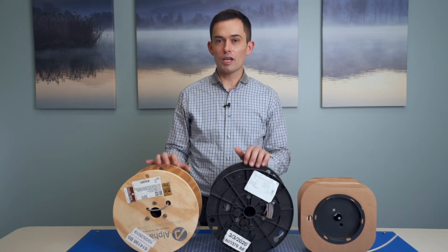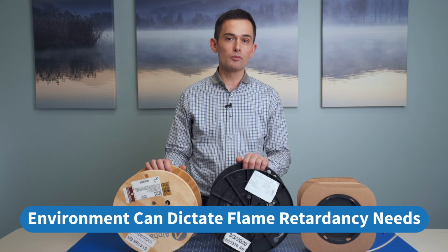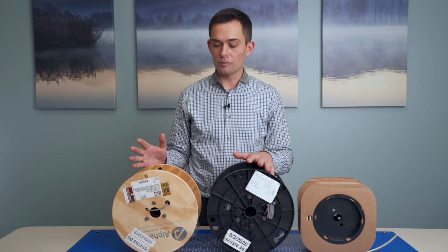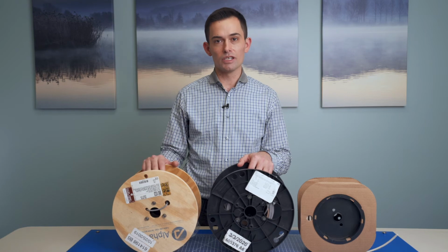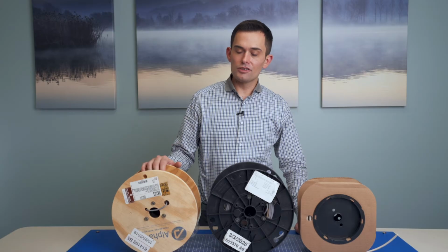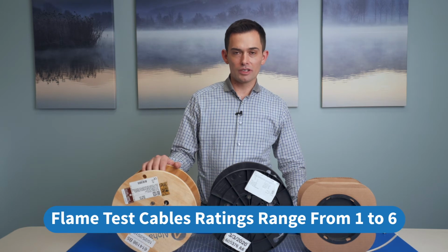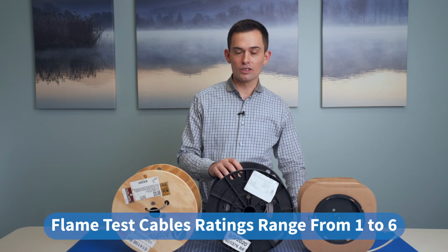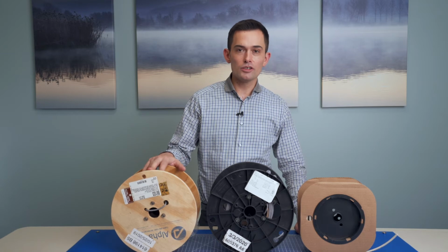Additional flame retardancy above and beyond standard AWM recognized component cable and wire is going to be necessary if your cable is going to either be installed in a plenum or riser environment, or if it's going to be used as the power cable for your assembly. Lifespan and expectancy is not so much of a consideration when it comes to choosing a particular UL type, but it is important when you're looking at what type of environment the cable is going to be installed in. That's where it gets critical. You might need FT1, you might need FT4 for flame retardancy. It all depends on what type of environment the cable assembly is going to be installed in.